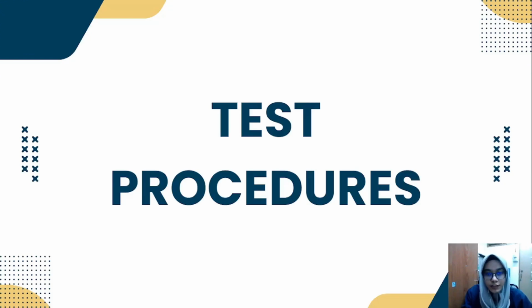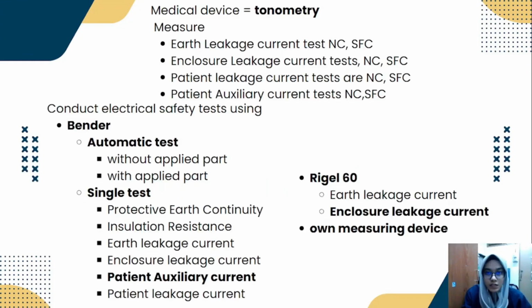And I will continue with the test procedure. Our medical device is tonometry, and we need to measure the earth leakage current, enclosure leakage current, patient leakage current, and patient auxiliary leakage current under the normal condition and single fault condition. So to conduct the electrical safety test, we will be using the Bender for automatic test and single test, the reference device, and our own measuring device.